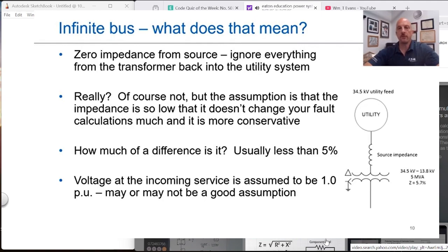That becomes especially important when you're doing things like fault calculations and even harmonic analysis, to be honest with you, for resonance and things like that. So if you can understand transformer impedances and calculate all that, then you can figure out how that comes together. How much of a difference is it? It's usually less than 5%. And in fact, it errs on the conservative side. If we ignore that impedance, we're making the impedance lower. If the impedance is lower, our fault current is going to be higher, so it makes for a more conservative calculation. Now, what if our per unit voltage is not 480 or 13.8 kV, but maybe 5% high? Again, we have to think about that. So we may actually add a little bit of fault current into our final calculations.